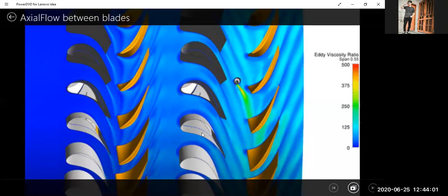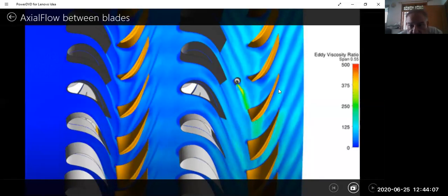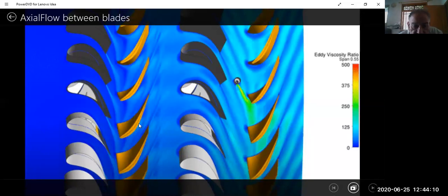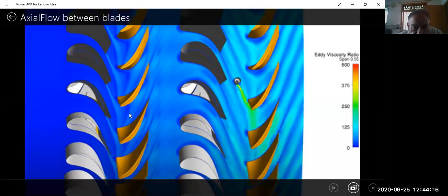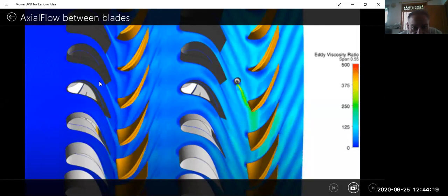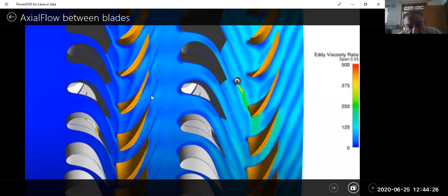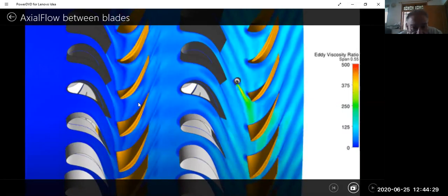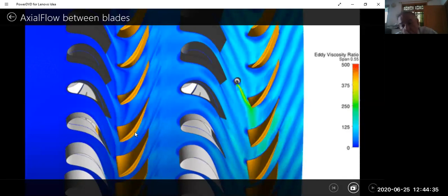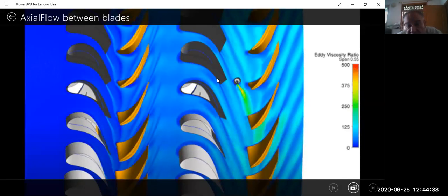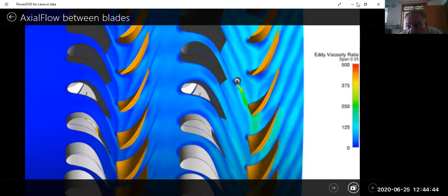So this is computer animation. Here is stationary blade. This is stationary blade row. This is moving blade row. And inside fluid is shown. This is computer simulation. So fluid enters here, then touches with the moving blade which comes in front of this nozzle. This is nozzle. And at the blade exit the direction is changed. And because of this reaction force and because of change of momentum, this wheel gets a tangential force, and because of this tangential force, blades are moving. Then this is the next stationary row. This changes the direction of the fluid for the next moving row, and like this, fluid flow continues.